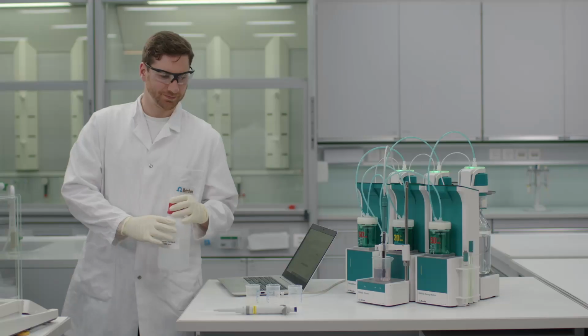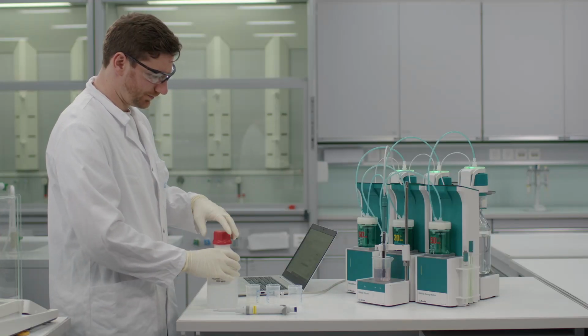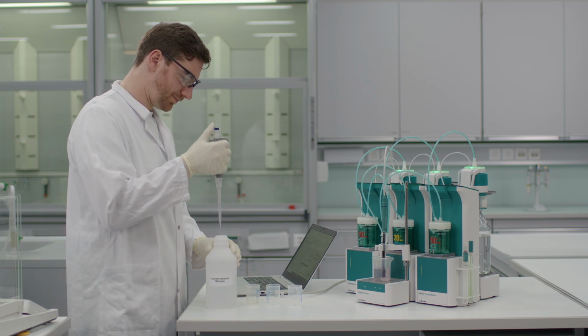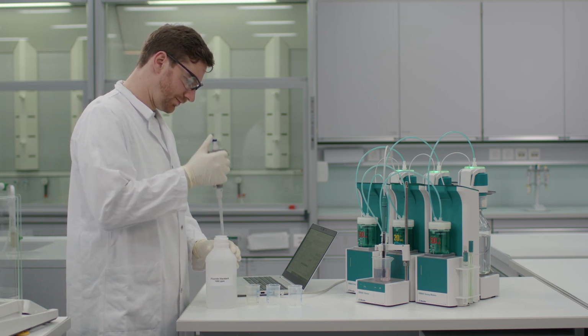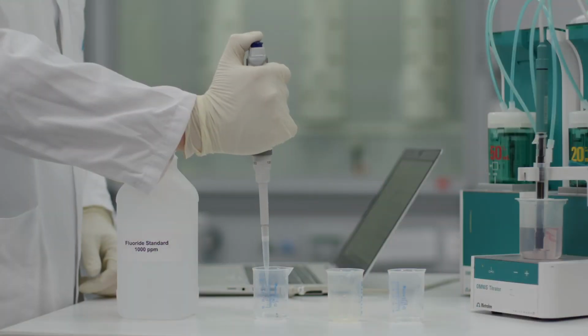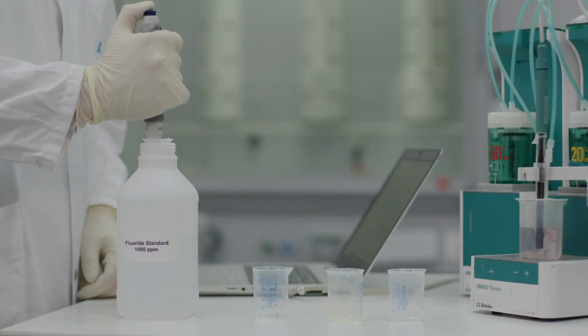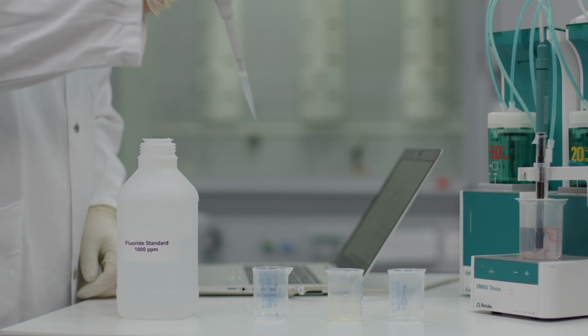So, let's look at the direct measurement. Before measuring the sample, you need to calibrate the sensor. For this, you need to prepare several standard solutions. An Omnis dosing module can also be used to prepare them from a single calibration standard. This will increase the reliability of your results.